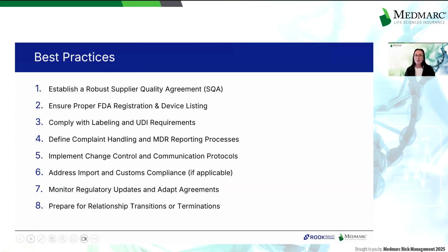For some of you, this may have been a lot to take in. So let's highlight these best practices. Whether you're the private labeler or the original equipment manufacturer, it's essential to follow these key guidelines to ensure regulatory compliance and operational success. Establish a robust supplier quality agreement to clearly define the roles and responsibilities related to design, manufacturing, labeling, complaint handling, and regulatory reporting. Ensure proper FDA registration and device listing. The original manufacturer must list the device with the FDA, including the private labeler's brand name. The private labeler is typically registered as the distributor.